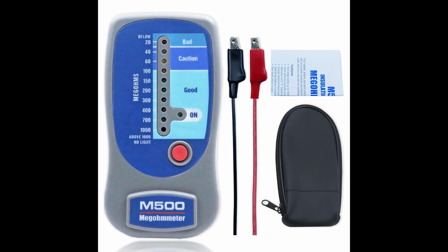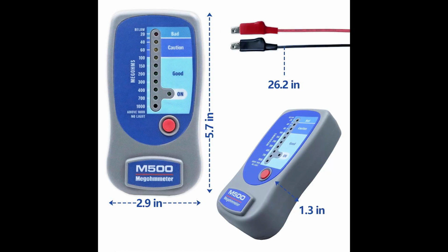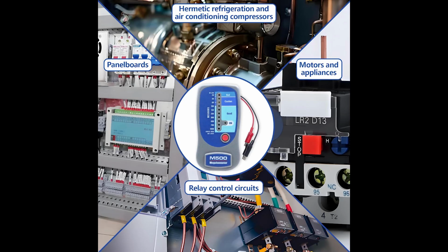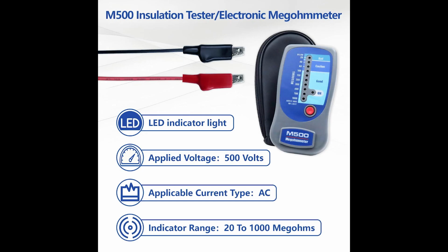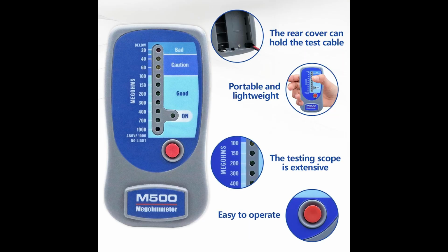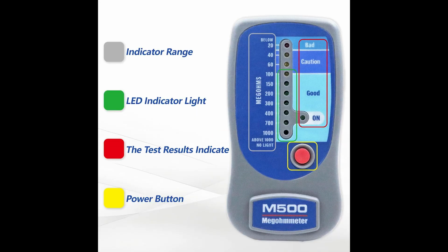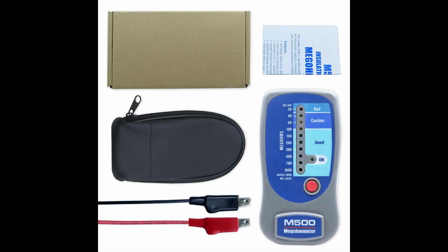Here's the tool that prevents catastrophic failures: the M500 Insulation Tester Megohmmeter. Every pro knows a winding failure is a death sentence for a motor or compressor. This device injects a high-voltage charge, 500 volts, to check the insulation resistance up to 1,000 megohms. The best part? It uses a simple good, normal, risk LED zone scale, so interpretation is instant. Use this for preventive maintenance, and you'll save your clients thousands.